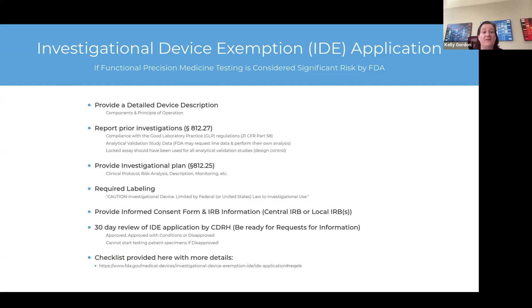The other big thing that I see a lot of issues with IDEs getting through is just not using the appropriate FDA-recognized analytical validation terminology. So it's really important. Is it a qualitative assay? For example, if it's a patient selection assay, enroll in trial, don't enroll in trial, it's probably qualitative. So you want to do all your validation in that way because it's going to be less burden. I won't go into too much detail on the different ways to validate today, but just to give you an idea to keep this in mind.